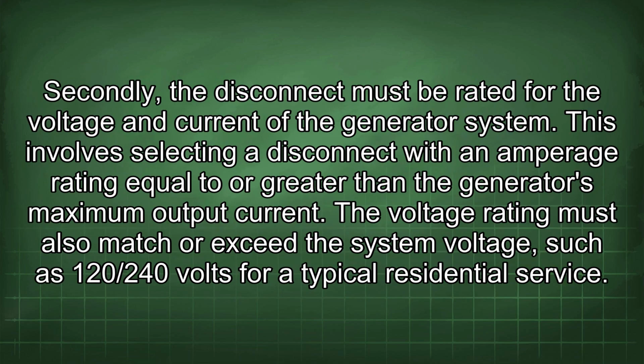Secondly, the disconnect must be rated for the voltage and current of the generator system. This involves selecting a disconnect with an amperage rating equal to or greater than the generator's maximum output current. The voltage rating must also match or exceed the system voltage, such as 120/240 volts for typical residential service.